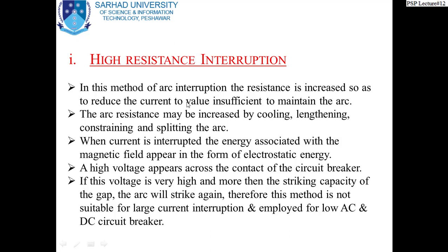So, gentlemen, how can we increase the resistance between the two contacts? There are different methods used. The arc resistance may be increased by cooling, because cooling also increases the resistance. Lengthening: if we have some method to lengthen the arc, naturally when the length is increased, the resistance will be increased.